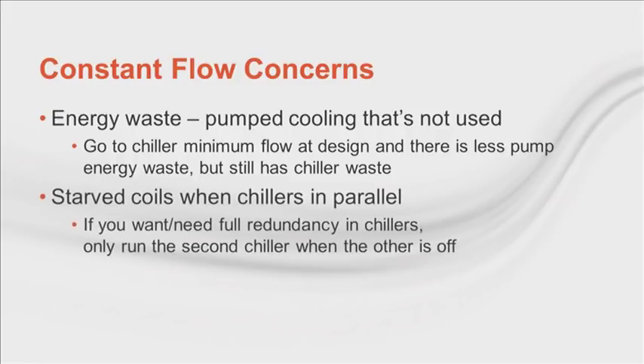The second limitation is when you have 2 or more chillers in parallel, if and when you operate the system with both chillers rather than just for redundancy. We talked about this in the 2004 and 2008 broadcasts. Dropping a chiller and a pump means your coils could be starved for flow. And if you leave flow through the chiller that's off, you don't meet the pump isolation requirements of the energy codes and standards. You mix chilled water and return water, and you waste energy. If you have a variable speed drive on the pump, you may be able to overpump the operating chiller, provided you stay within the limits of the chiller.